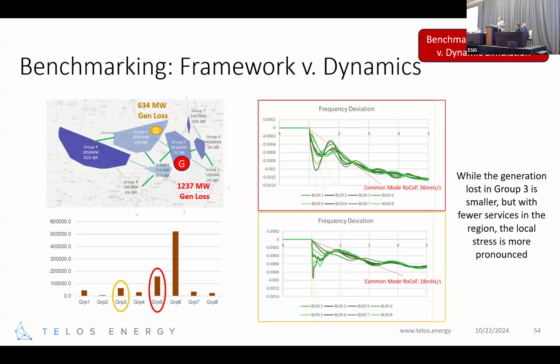And so from the common mode standpoint, you can see that the loss of the larger unit has a higher rate of change of frequency (RoCoF) of the common mode, which you would expect. It's about twice that of the RoCoF of the common mode system response from this smaller generator. So yes, you're hitting the system twice as hard. That's about what you would expect.